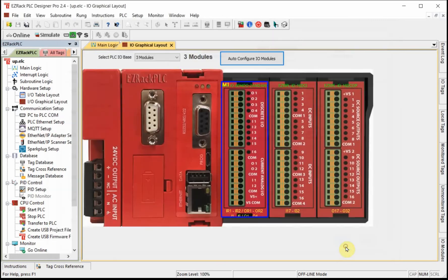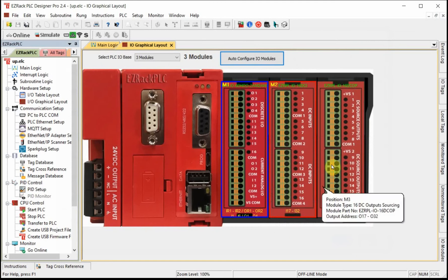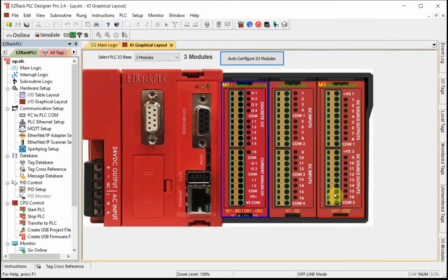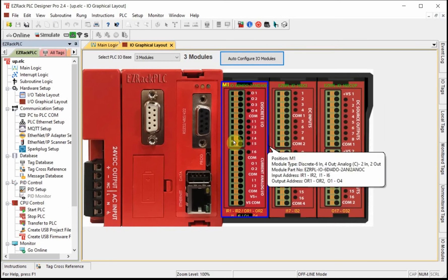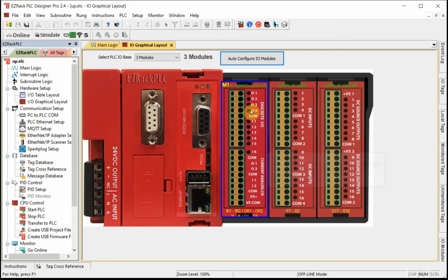I've noticed that on this controller it consistently misreads the multi-function card. There are two varieties: a voltage output and a current output. We have the current output, so you'll want to select the NOC card. I have two other cards as well, which are correct. If you don't see this screen you can't really program any IO — you need to see at least this one module, the controller we have in class.